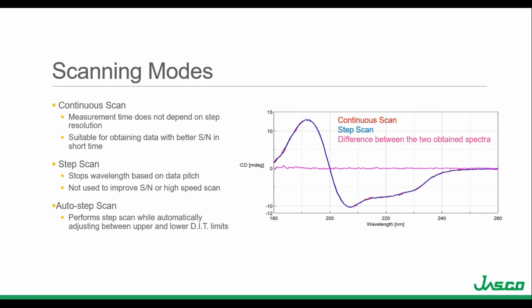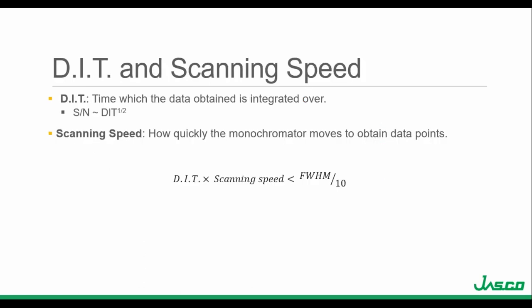The figure on the right shows a continuous and step scan overlaid in red and blue respectively, with the difference shown in pink — there's virtually no difference between the two scans if the correct measurement parameters are selected. Going forward, I'll assume we have selected the continuous scan mode. The DIT and the scanning speed are extremely important to optimize for accurate data and good signal to noise. The DIT is the digital integration time — the time in which the data is integrated over. The detector sees incoming photons and passes them along for signal processing; the DIT specifies how long the detector sees these packets before sending information to be digitized. The square root of the digital integration time is proportional to the signal to noise.